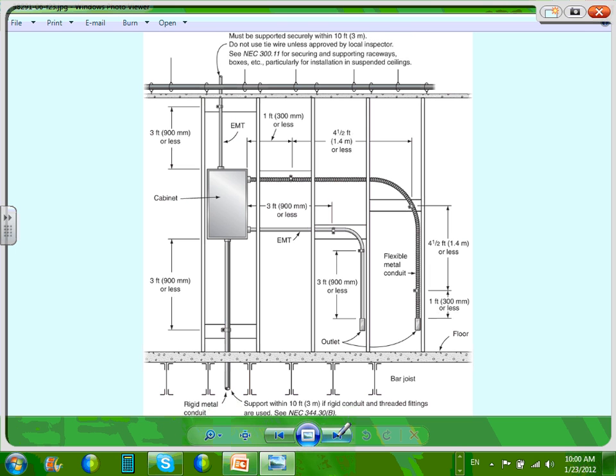If you have an EMT conduit, you have to support it every 3 feet of every box. Every 3 feet of every box. Can you guys see that? The support right here. If you have an EMT conduit, the same thing: EMT support at intervals. The intervals of EMT, guys, here's another box here, every 3 feet, and most of the time 3 feet from every box and 10 feet in between.